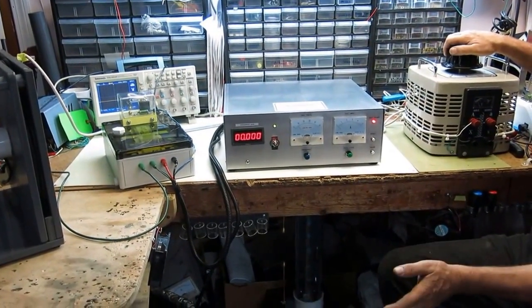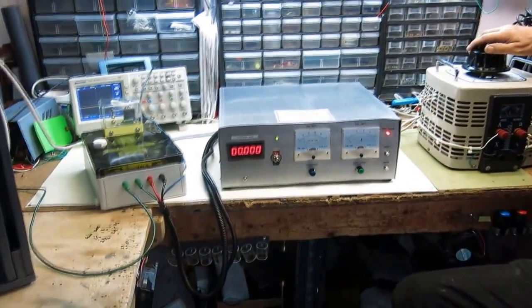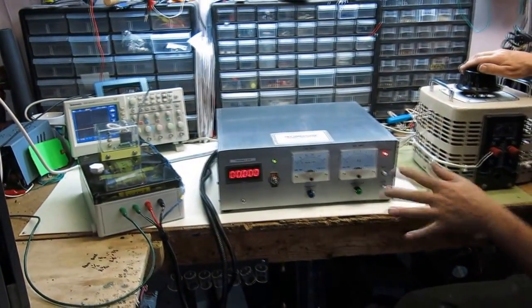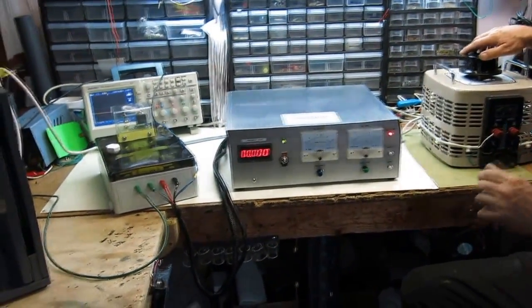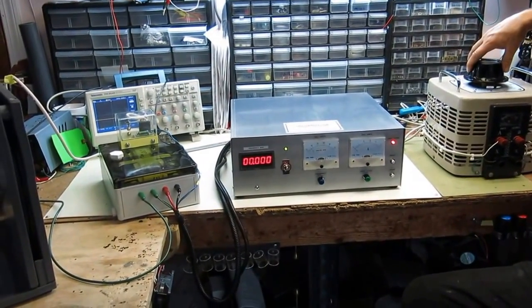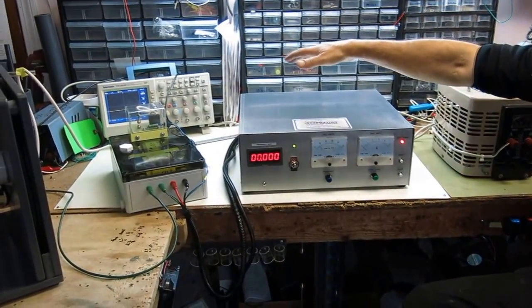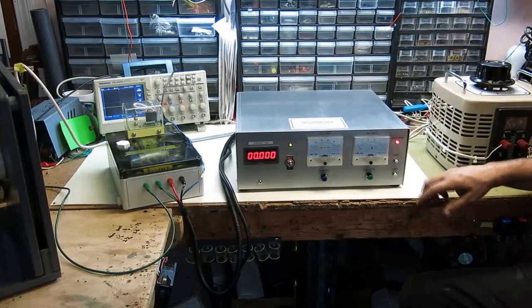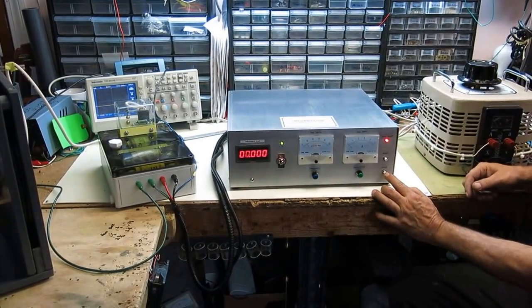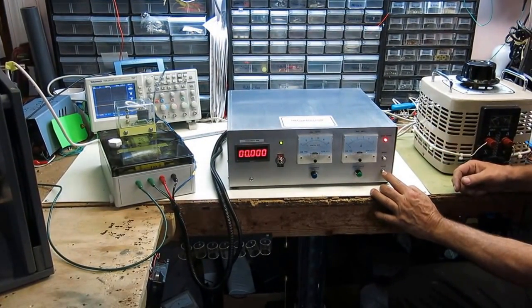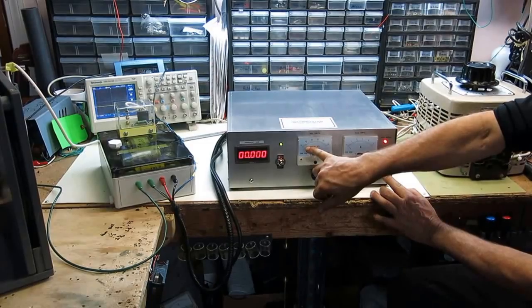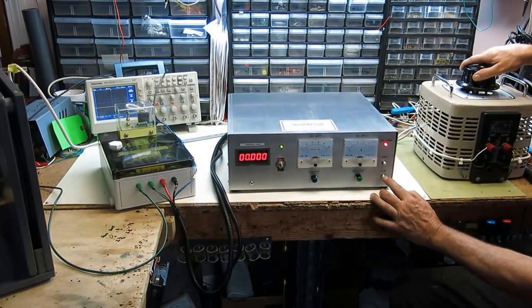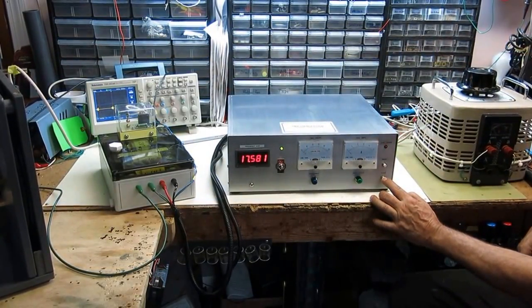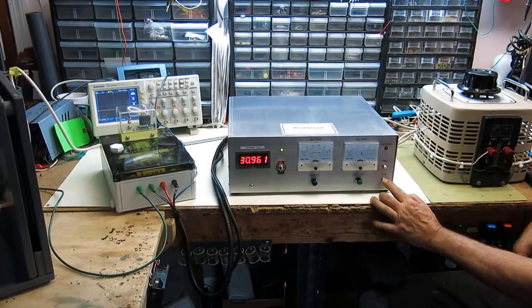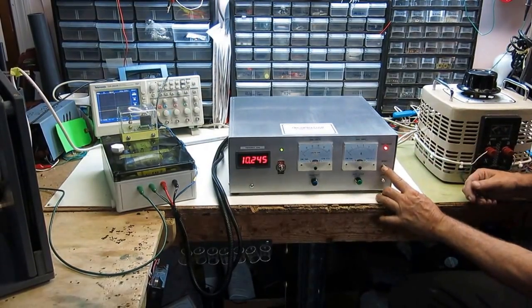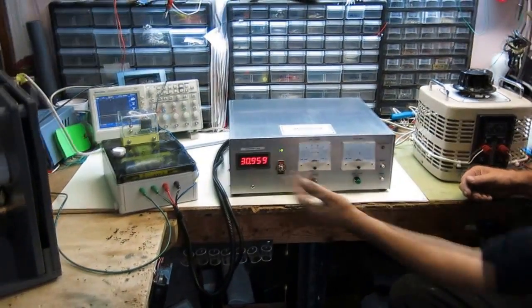When it does happen, it shuts down the signal to the amplifier circuit, so you have to turn your variac down. Because there's such a large capacitor on the amplifier circuit, you have to drain that power off before you can reset. This button that says drain, you'll see it's still holding charge even though there's no voltage going in, and it'll go through the transformer and out to zero. Then you get reset and your frequency comes back on.